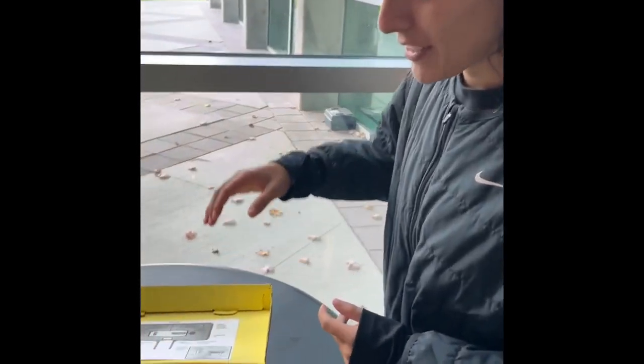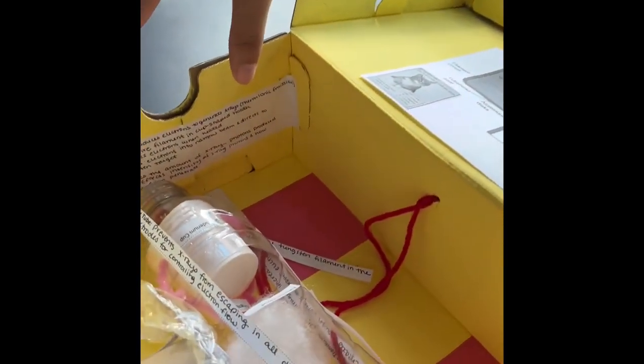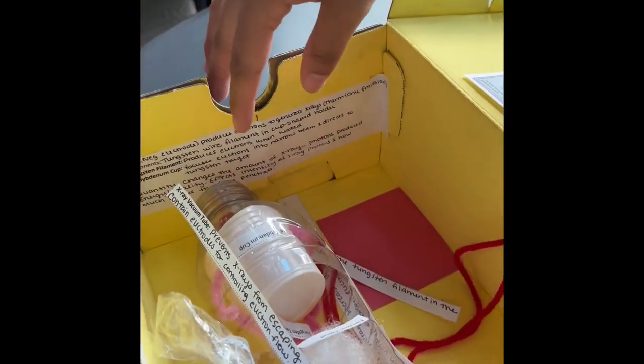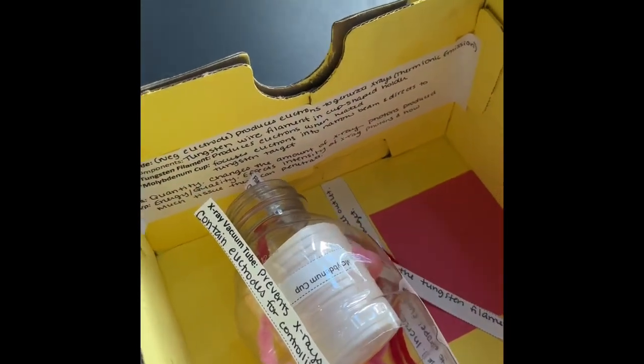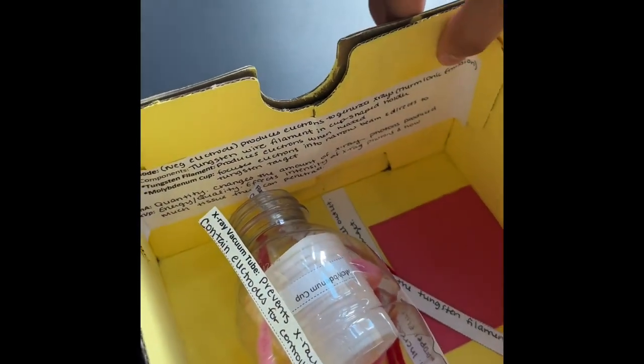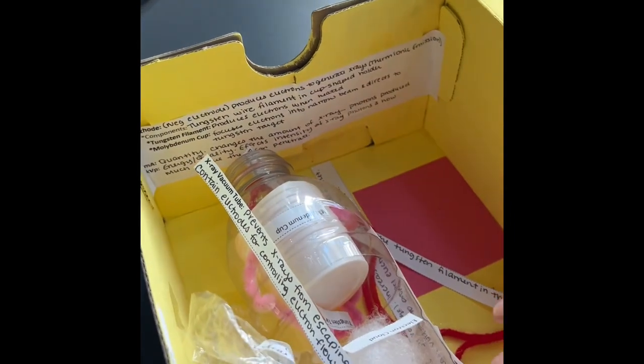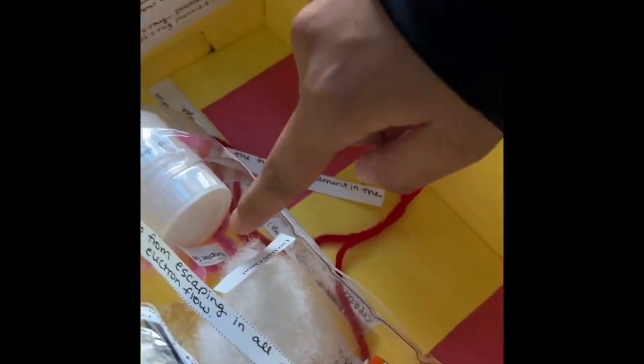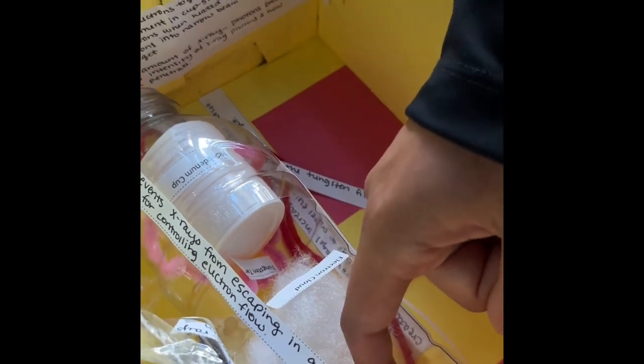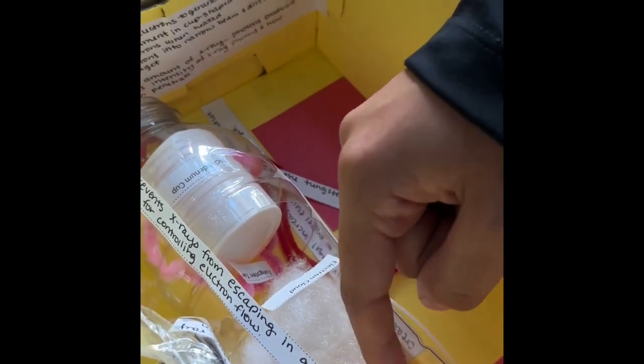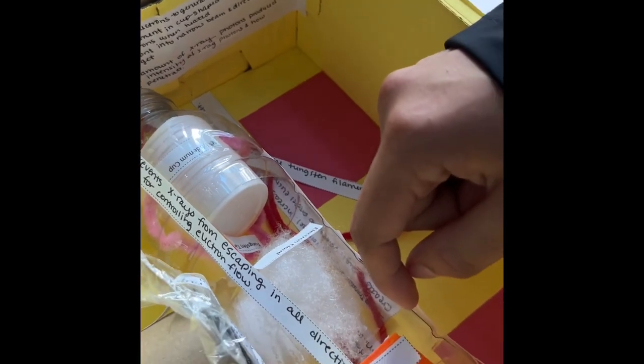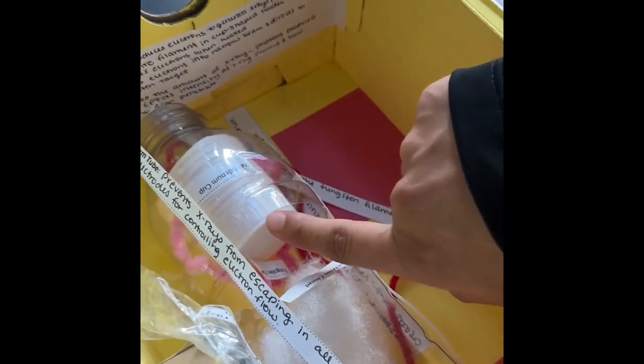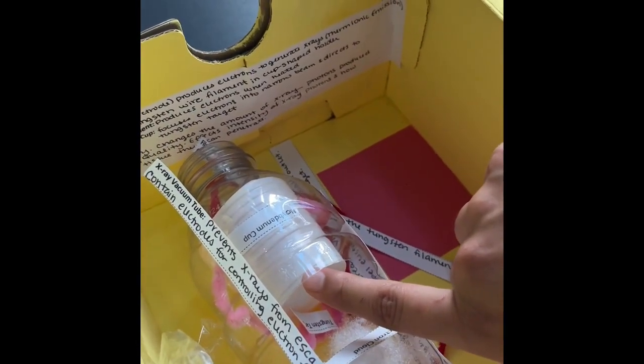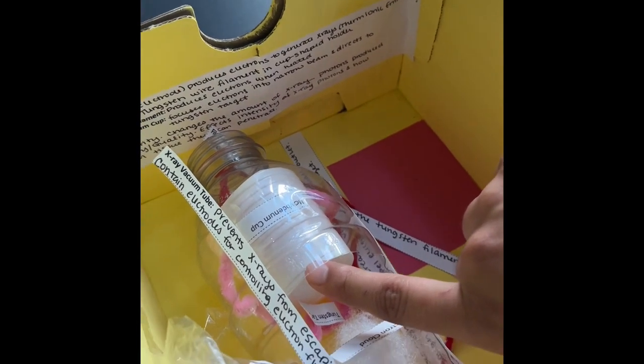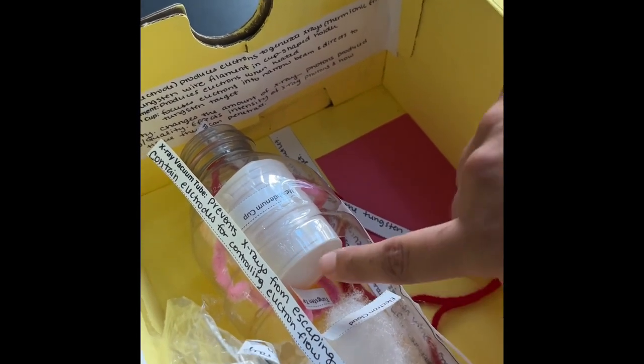Hello, if you come over here, this is the cathode. It's known as the negative electrode, and it produces electrons to generate X-rays, known as thermionic emission. And if you look right here, some of the components it has is the tungsten filament, which is on this side of the cup, or of the copper stem, and that produces electrons when heated. And then the molybdenum cup focuses electrons into a narrow beam and directs them to the tungsten target.